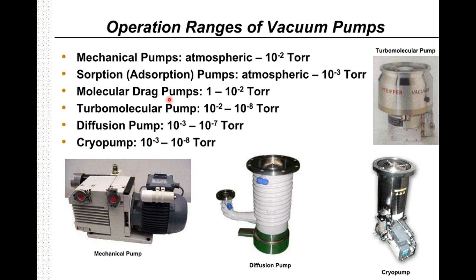The molecular drag pump operates from 1 to 10⁻² Torr. The turbo molecular pump has an operation range of 10⁻² to 10⁻⁸ Torr. The diffusion pump operates from 10⁻³ to 10⁻⁷ Torr. The cryopump has an operation range from 10⁻³ to 10⁻⁸ Torr.